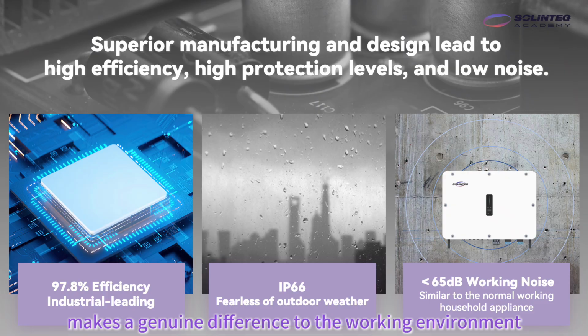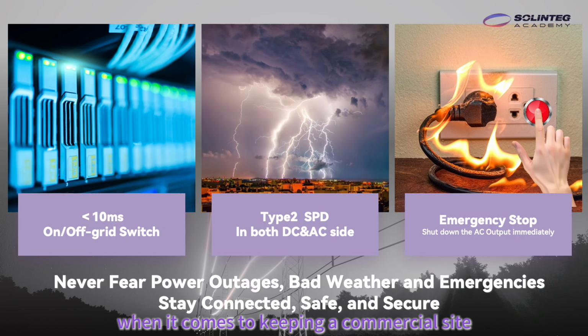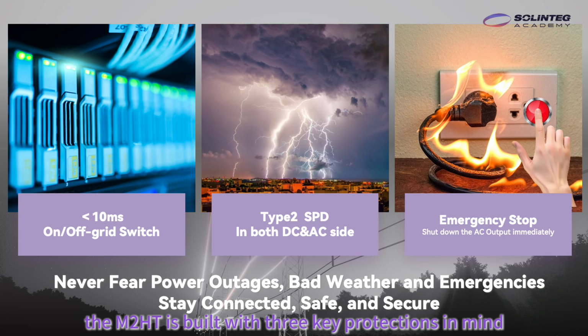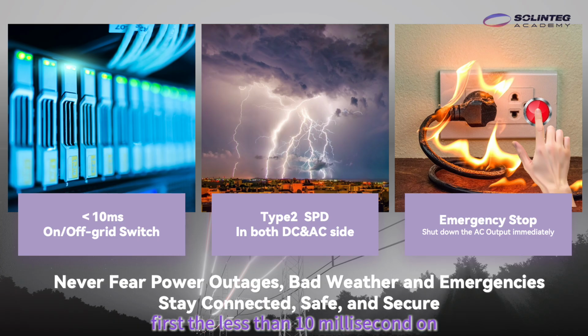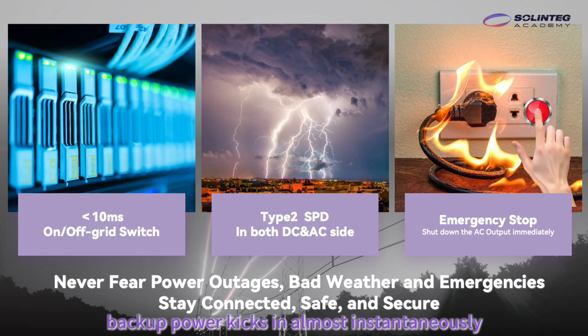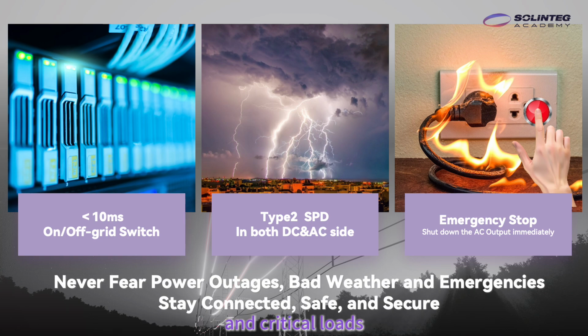to the working environment. When it comes to keeping a commercial site safe and operational, the M2HT is built with 3 key protections in mind. First, the sub-10 millisecond on/off-grid switching time means that when the grid goes down, backup power kicks in almost instantaneously, fast enough that sensitive equipment and critical loads experience no meaningful interruption.